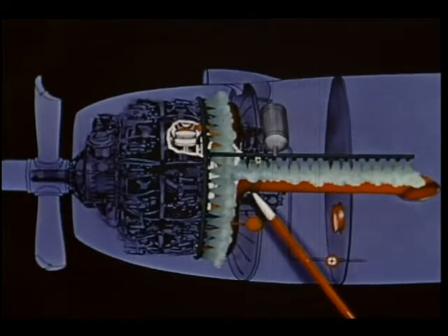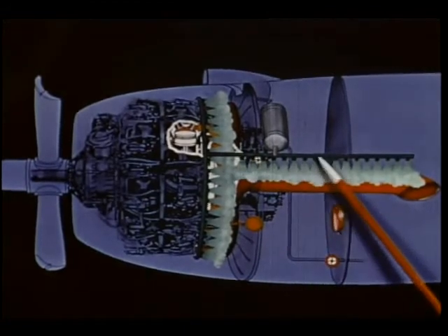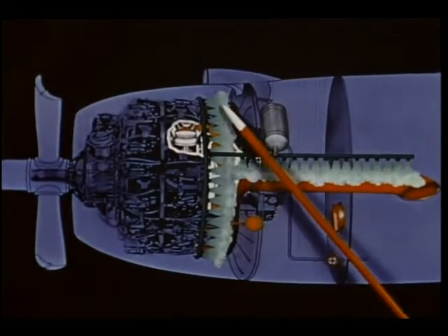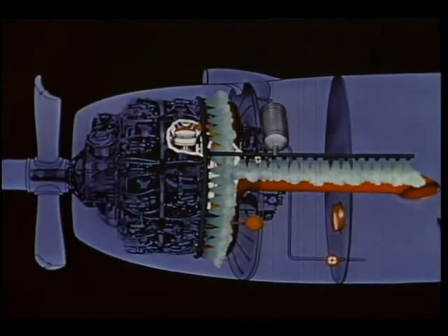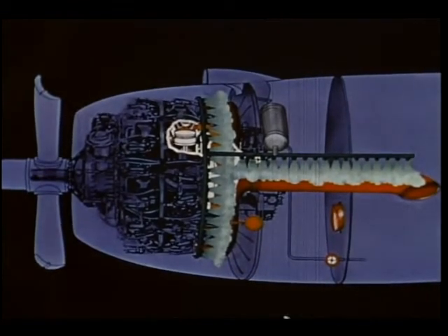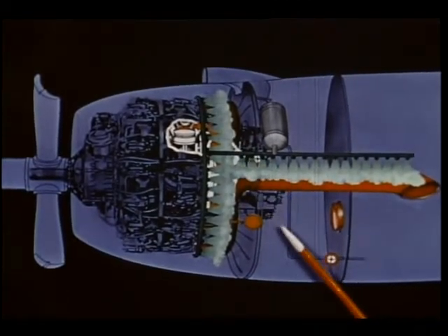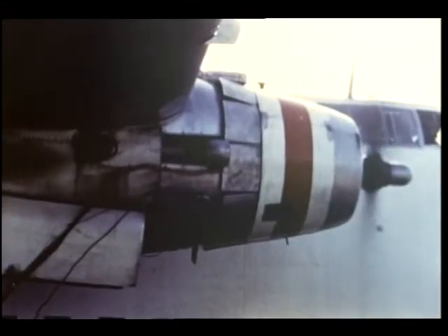In order to prevent ignition on the hot metal of the exhaust system, a water spray is used to cool all of the exposed metal which is hot enough to ignite the combustible. In the few seconds needed to cool the metal to safe temperatures, an inert atmosphere of steam, generated by the water evaporating from the metal itself, shrouds this potential ignition source to render it impotent. The portion of the water spray system which services the exhaust collector ring is this 3/4-inch diameter tubing, bent to conform approximately to the shape of the collector ring. The exhaust system receives water over its entire surface from its spray nozzles.